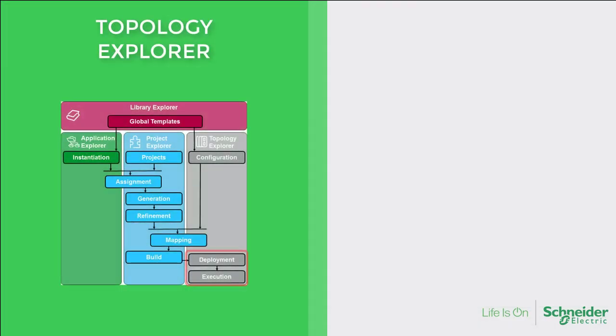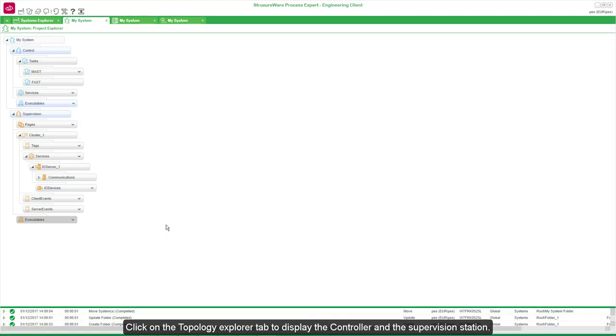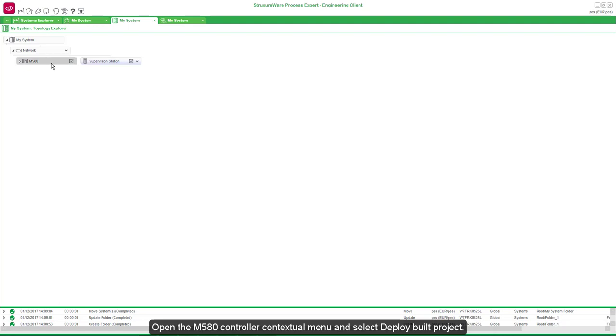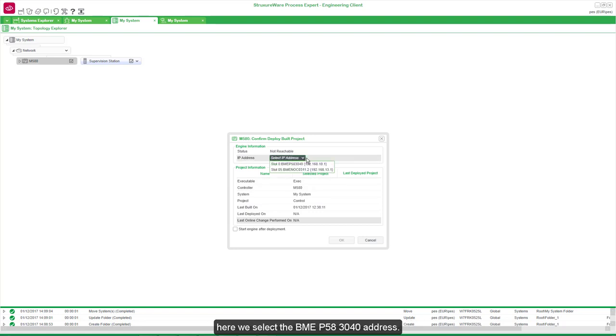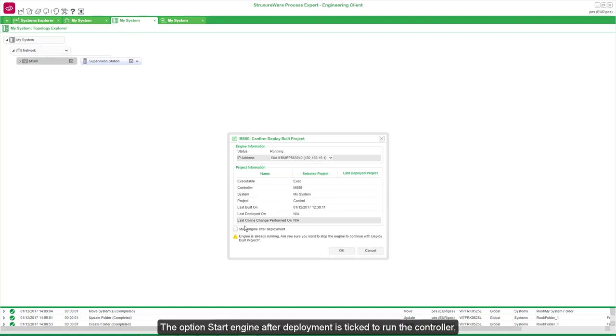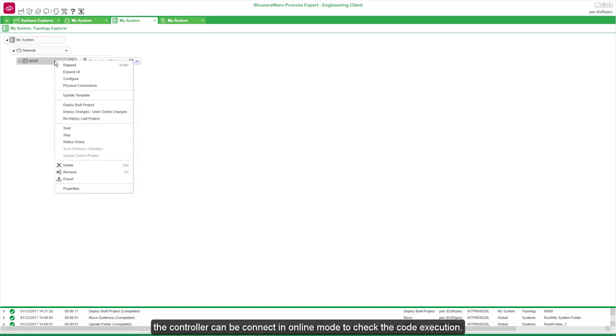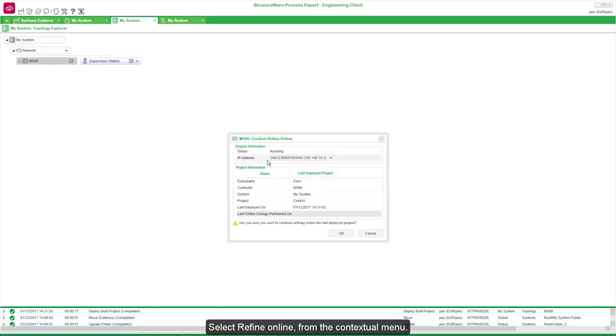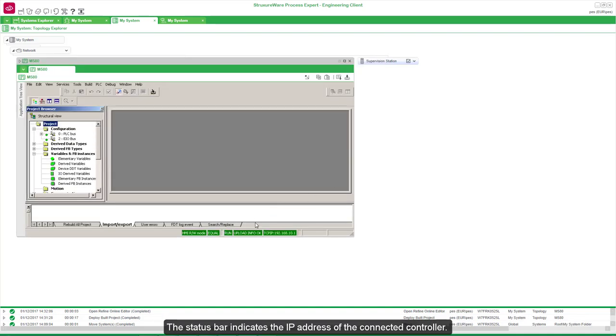Deployment is done from the Topology Explorer. The control project will be deployed to the M580 controller, and the supervision project to the supervision station. Click on the Topology Explorer tab to display the controller and the supervision station. Open the M580 controller contextual menu and select Deploy Build Project. The executable mapped to the M580 controller is displayed; confirm by OK. Select the IP address used to deploy the project — here we select the BME P583040 address. The option Start Engine After Deployment is ticked to run the controller. Click OK to validate the selection and confirm the deployment. When the deployment is complete, the controller can be connected in online mode to check the code execution. Select Refine Online from the context menu, check the information in the next window, and confirm the online refine.